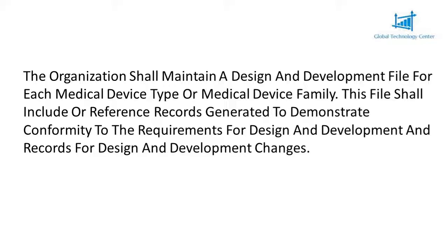The organization shall maintain a design file for each medical device type or medical device family. This file shall include or reference records generated to demonstrate conformity to the requirements for design and records for design changes.